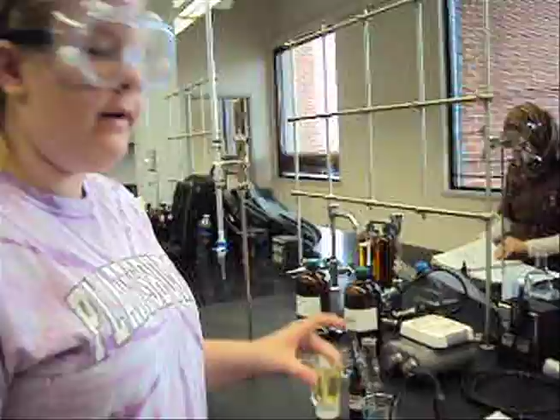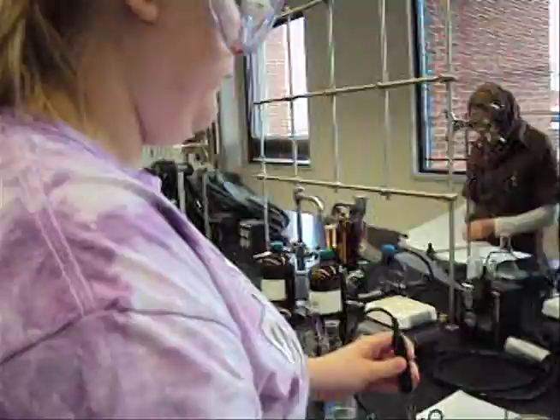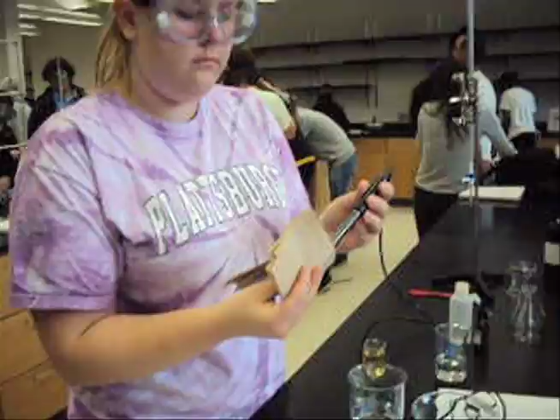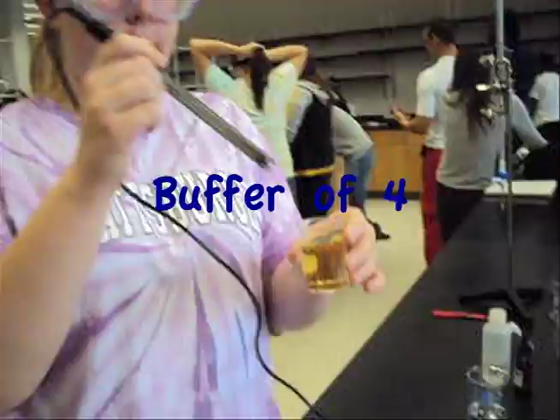And so now we want to calibrate it to measure acid. So we have a buffer solution of pH 4. So again, dry off the electrode, and place it into the buffer solution and swirl it. So just rinse it off again and place it back in the water.